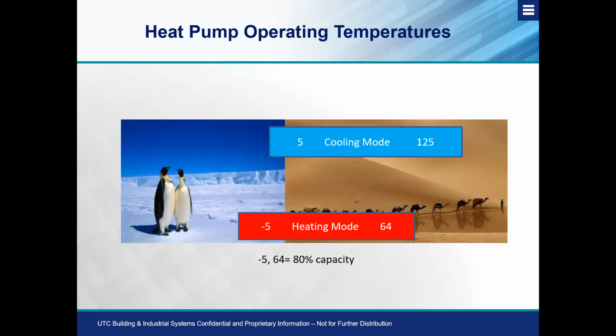So heat pump operating temperature ranges. So for the cooling unit, we can operate all the way down to 5, all the way up to 125 degrees. And then for our heating mode, we can operate down to -5, all the way up to 64. Remind you the same rule applies to the discussion with the heat recovery side of things. This all is derived based on whether we have a single unit, in this case for heat pump, twin or triple unit, and then the connected capacity, compressor and coil surface area.